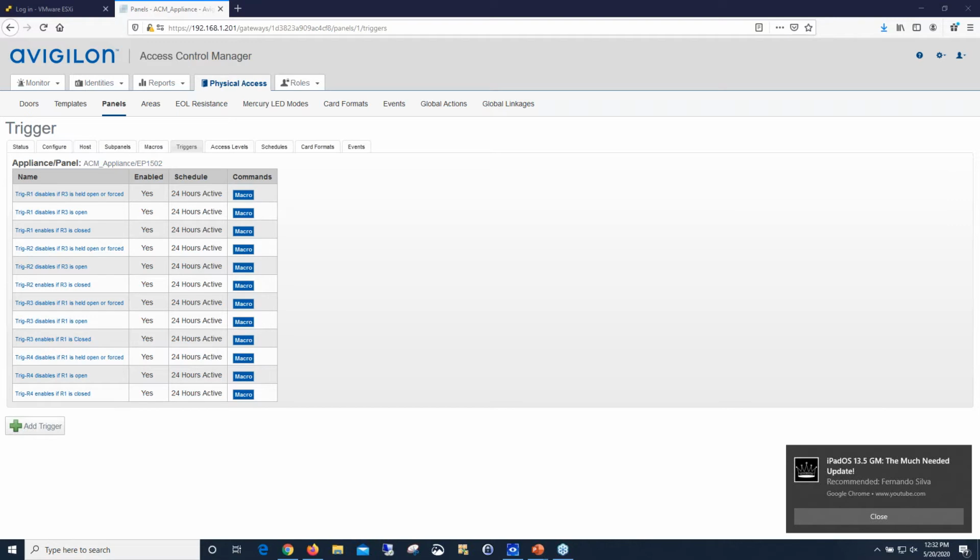But my guess would be that you would probably use some type of pneumatic button. And assuming you're using maglocks to control those doors, you probably run your positive power through that, the power coming from the power supply directly to the maglock. You'd probably run the leg of the power through that pneumatic button. So if you press that pneumatic button, it breaks power directly to the maglock and lets you out regardless of what's going on with the access control system. That would be my guess on how the AHJ would handle it. But again, always check with the AHJ to make sure that's the way they want you to handle an emergency.